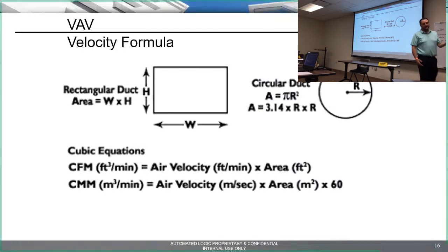And you're wondering, well, why are you getting so technical? Why are you getting all the way down to that level? Because that's usually the number one problem. We'll get into problems in a little bit. The problem we generally have with a VAV is going to be airflow, most often. Maybe it's possible that the velocity pressure tubes could get dirty and not measure airflow properly, though you guys will probably all be retired by the time that happens. But we had a problem a long time ago at Baptist Hospital. We were doing test and balance. I was trying to calibrate this VAV box. This is an old pneumatic VAV box. Same principle, it works the same way, but we couldn't get the velocity pressure in, and we actually took instruments and measured it.